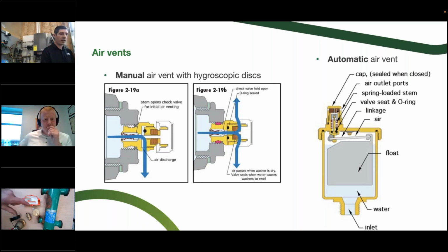Give that to you. So that is the same kind of technology with those little fiber gaskets, those little wafers in there, that if you put that on the top of the air vent, and this will fit on other brands of air vents as well, it's going to swell when it gets wet and it's going to close. So if you had an air vent above something that was really critical, not just above a boiler that's above a floor drain or something, and you really wanted to make sure under no circumstance does water come out of the top of that, you can just add that accessory right over an existing air vent to make sure that you seal up when the water is present, if that ever becomes an issue.